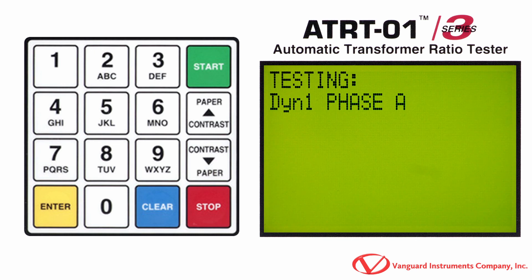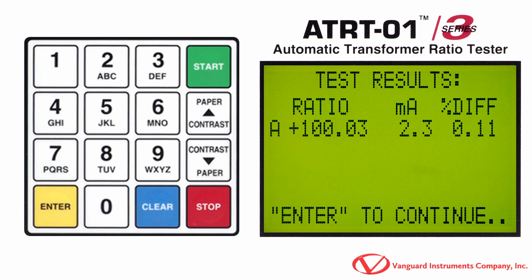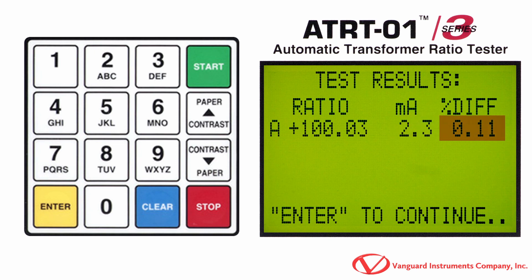After a few seconds, the test results for phase A will be displayed. The first column displays the measured ratio. The polarity is displayed as either a plus sign for in-phase or a minus sign for out-of-phase. The second column displays the excitation current. And if nameplate voltages were provided, the last column displays the percentage error, which is the percentage difference between the calculated ratio and the measured ratio. Press the Enter key to continue.